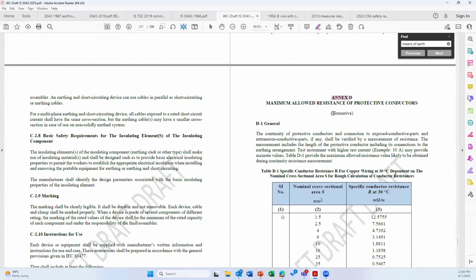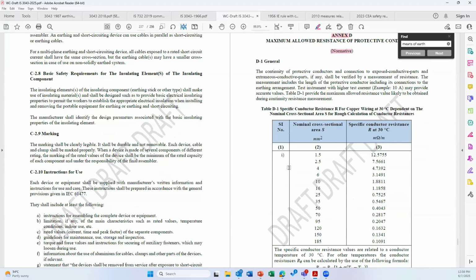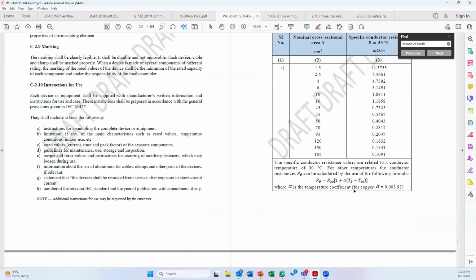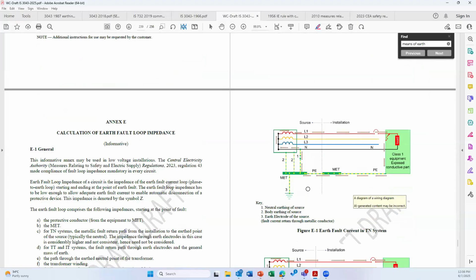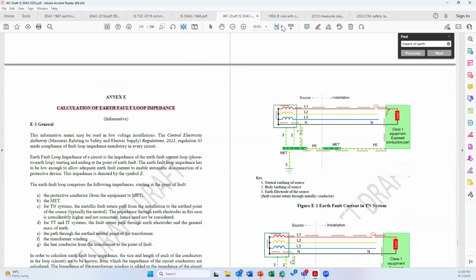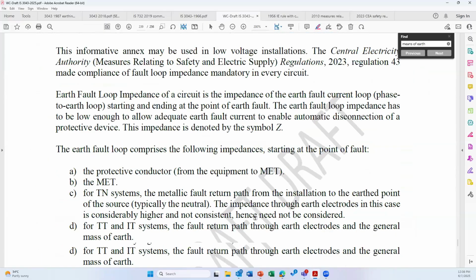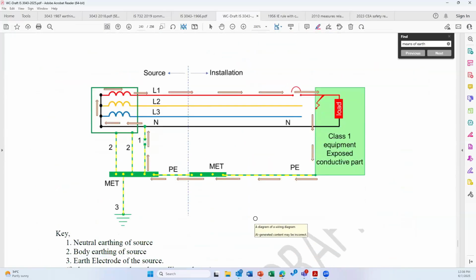Maximum allowed resistance, please note it's normative, it's not informative. Maximum allowed resistance of conductors for protective earthing is being included. Protective earthing and protective bonding is included. Then calculation of earth fault loop impedance as informative information is given. Just this particular picture explains what exactly is earth fault loop impedance. Please note that earth fault loop impedance measurement is mandatory. It has been included in the CEA regulation as well.